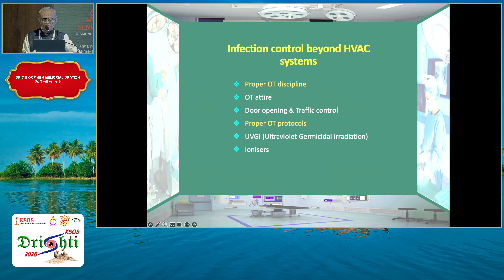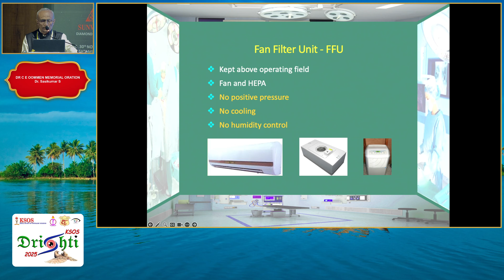This contains the fan filter unit, a device which contains a HEPA filter and a fan to blow filtered air over the surgical site. But there is no positive pressure, no cooling, for which you will have to install a split AC, and no humidity control, for which you will have to provide a dehumidifier.